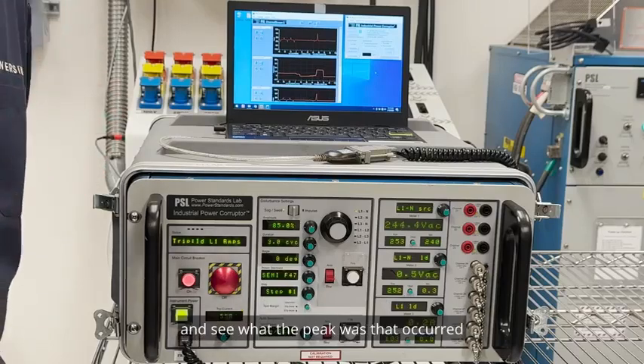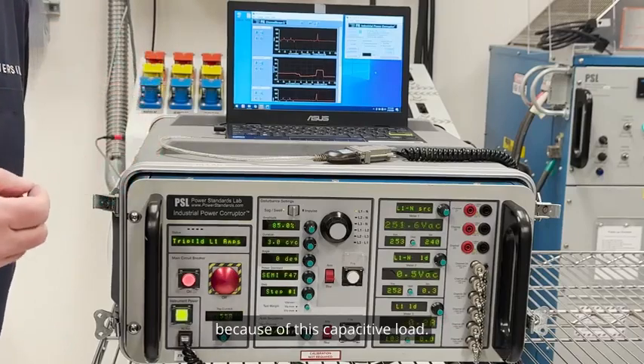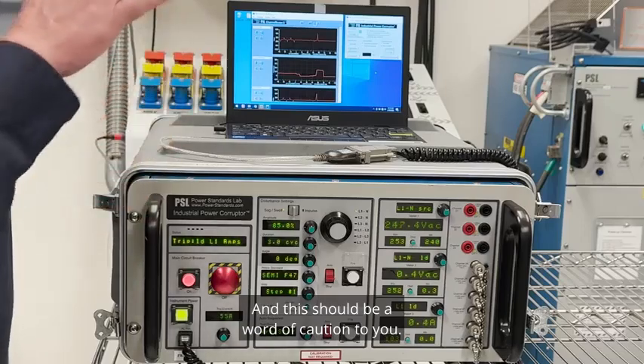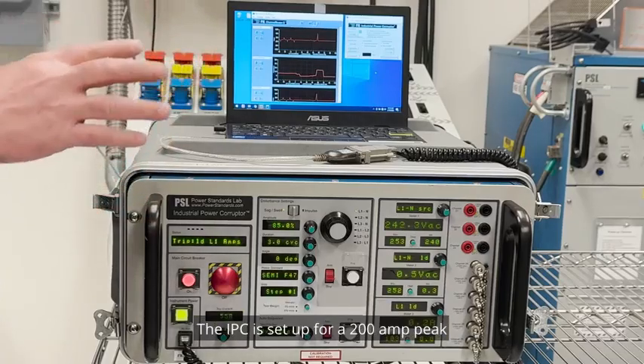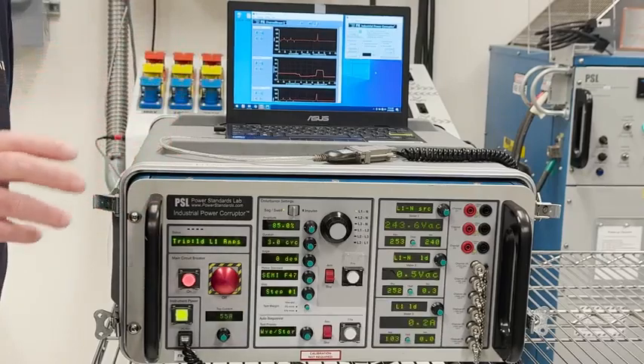Look at the curve shape and see what the peak was that occurred because of this capacitive load. And this should be a word of caution to you. The IPC is set up for a 200 amp peak in terms of inrush current.